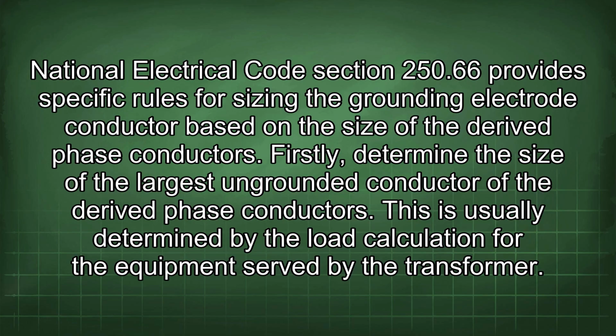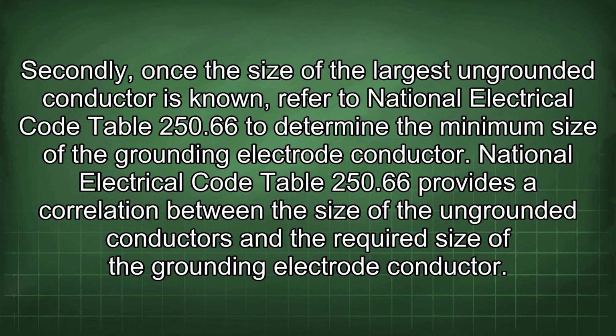National Electrical Code Section 250.66 provides specific rules for sizing the grounding electrode conductor based on the size of the derived phase conductors. Firstly, determine the size of the largest ungrounded conductor of the derived phase conductors. This is usually determined by the load calculation for the equipment served by the transformer. Secondly, once the size of the largest ungrounded conductor is known, refer to National Electrical Code Table 250.66 to determine the minimum size of the grounding electrode conductor.